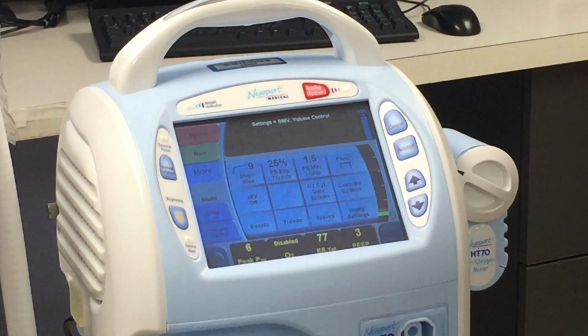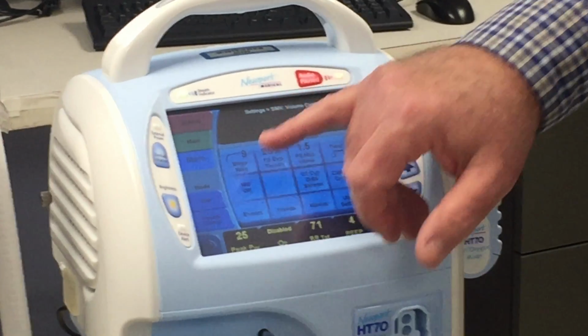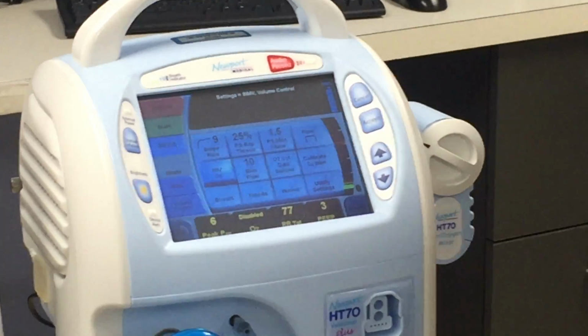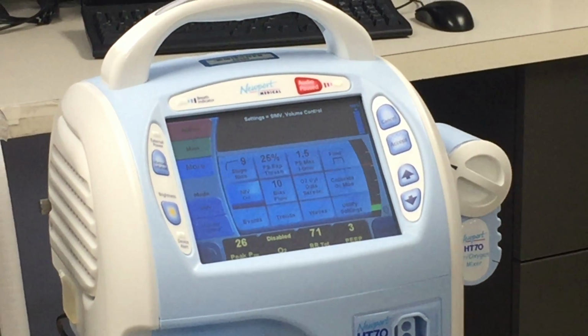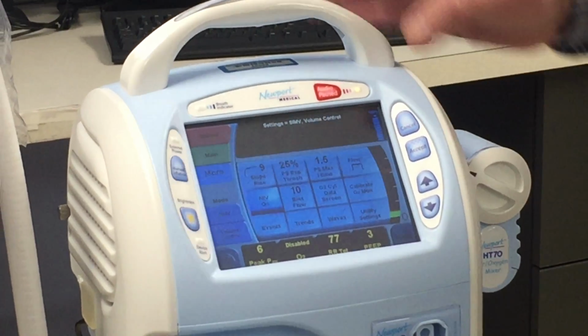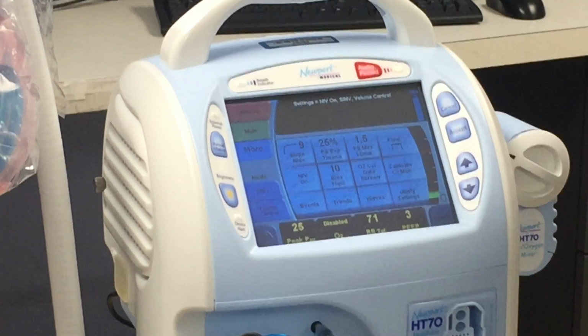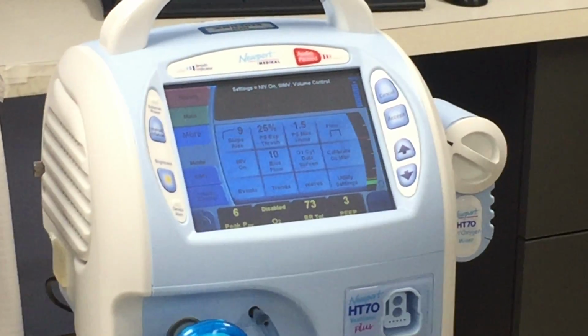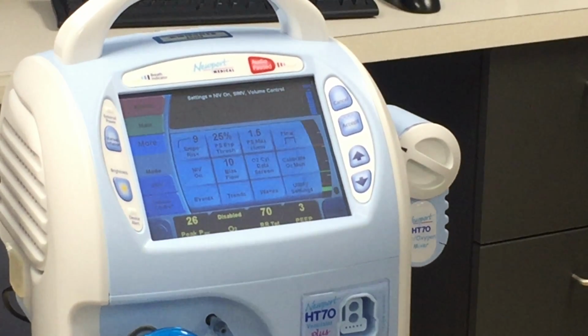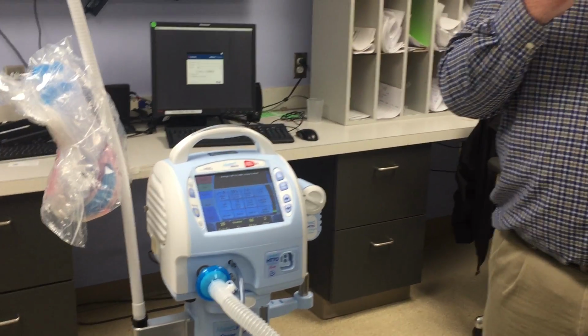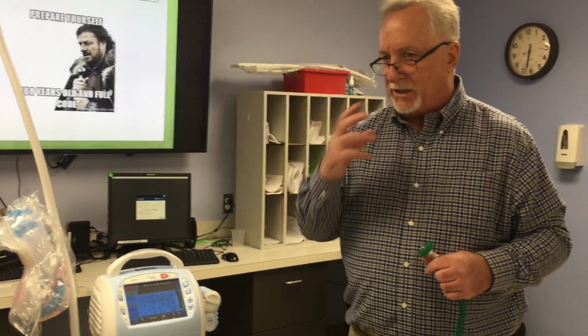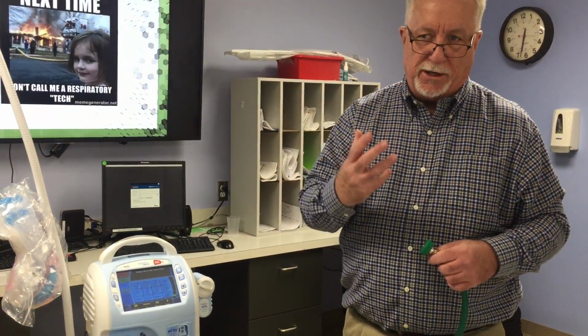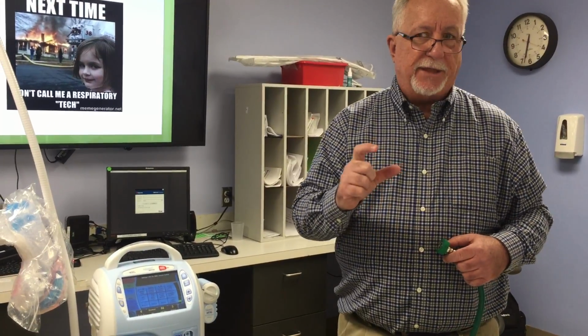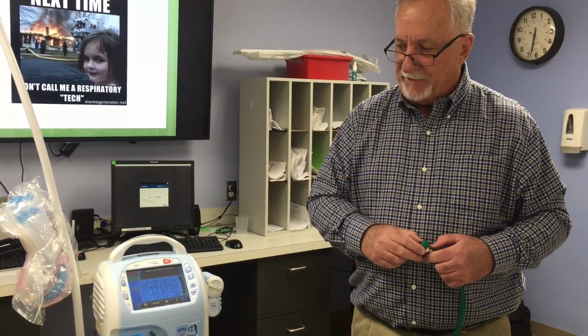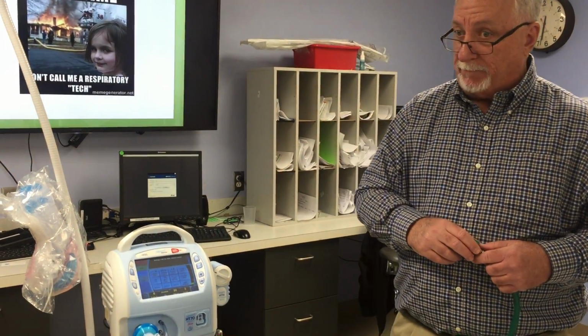Under more, you have some other screens. This is where if you wanted to turn the ventilator into non-invasive, you would turn it on, hit accept, and there's a bias flow for your leak. You would have to use a non-vented mask if you use it, because here's your exhalation valve here. So if you had used a mask with a built-in exhalation valve, you would get alarms because it would be leaking all the time. So you want to use a non-vented mask. They have the blue elbows on them for the non-vented, and you could use it that way as well.